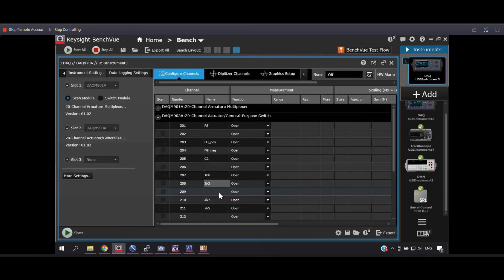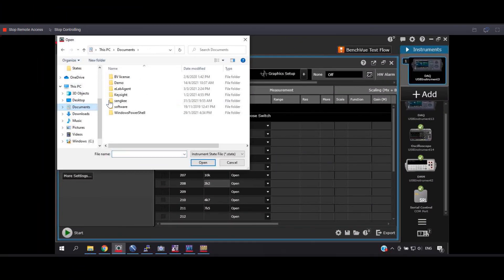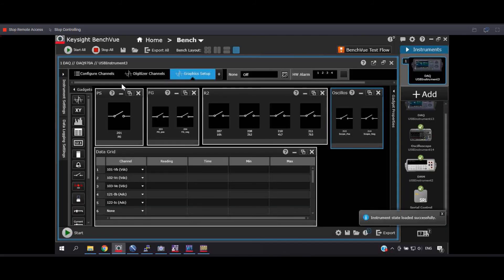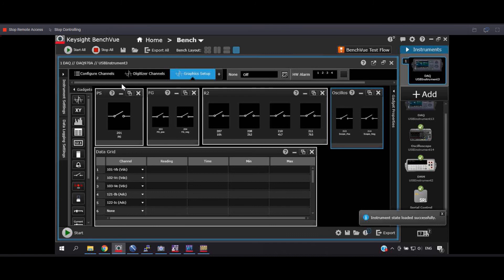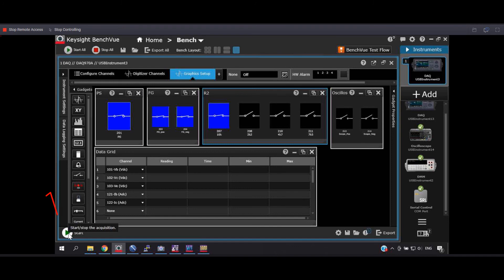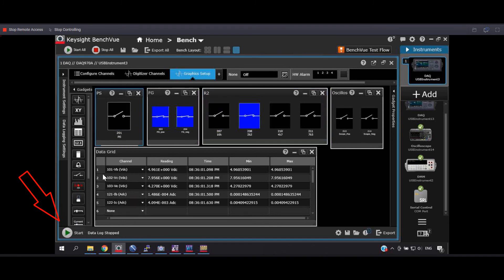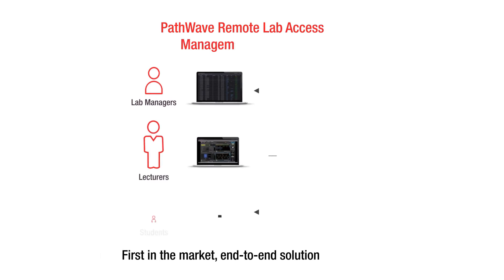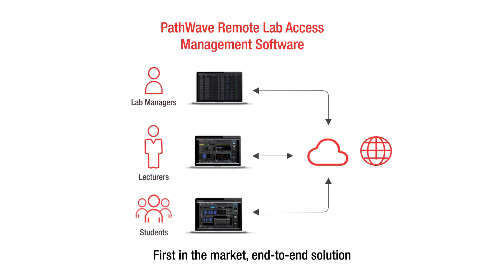Each module consists of 20 channels, and I configure the channels according to the connections and name the measurements accordingly. With all settings, connections, and configuration done, I am now going to load the state file. You can see all the switching gadgets I had set up are loaded. The first switch represents the power supply, the function generator, and the different input bias resistor values of R2. The data grid captures all the measurements, and you can always add a single measurement pointer. When I hit the start button, all measurements are taken at once. If I wish to see measurements for different input bias resistor values, I can do so by switching to other resistor values. You get more from your instruments when they work together, making your entire workflow more efficient.